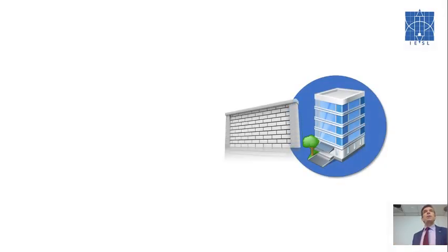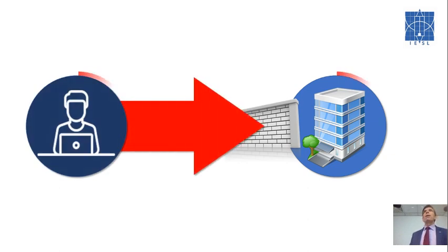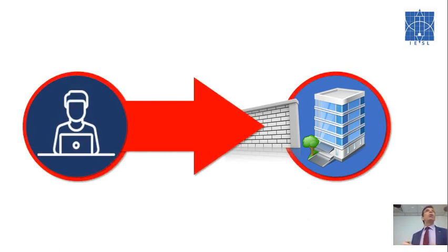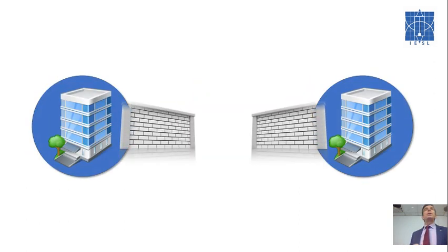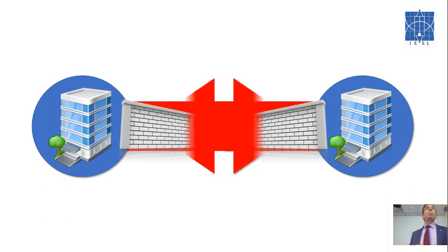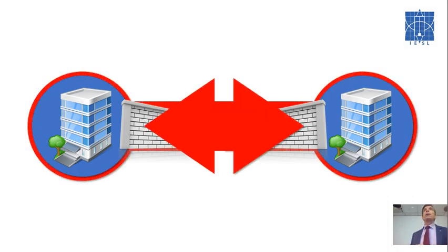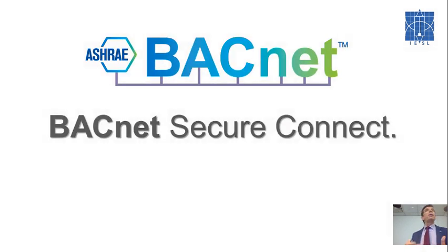Over the years, as Shodan has shown us, 30,000 systems are currently exposed to the internet, typically from the outside in, punching a hole in the firewall via port forwarding. Once inside a building, you could typically get to other buildings quite easily, again through punching holes from the outside in through firewalls. What BACnet actually delivered, starting in 2016, was Addendum BJ, which was incorporated into the standard SSPC 135 in 2018.